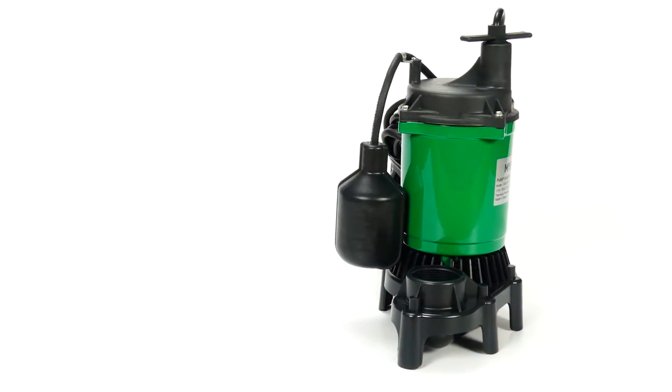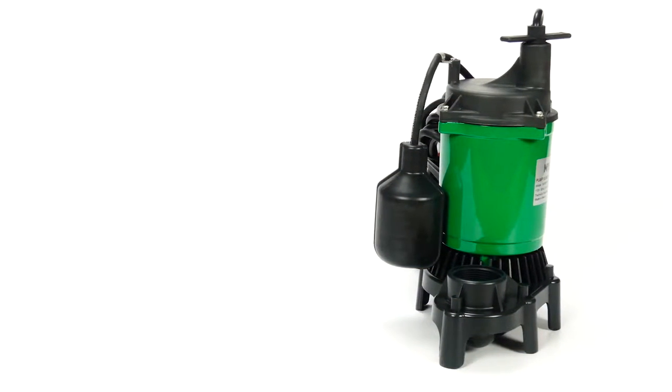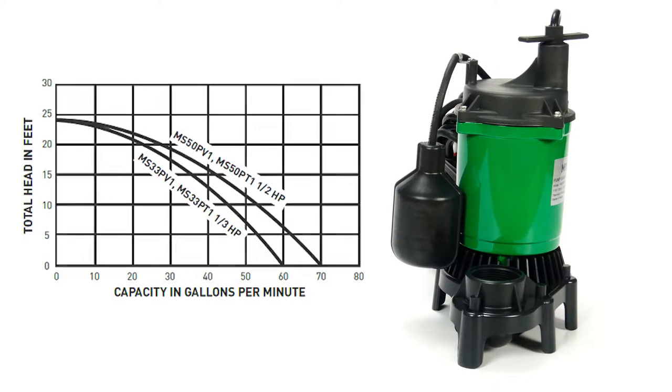Don't let the size of this pump fool you. This small lightweight pump can move an astounding 65 plus gallons per minute with a maximum shutoff pressure of about 25 feet, which is roughly 10.8 psi.